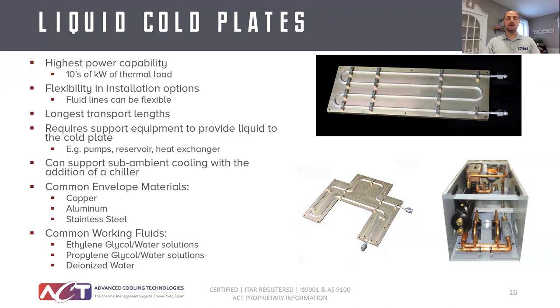Liquid cooling can support sub-ambient cooling if a chiller or chilled water is available, enabling liquid-to-liquid heat exchange to reject high amounts of energy below local room temperature. Envelope materials are most commonly copper, aluminum, and stainless steel. Working fluids tend to be glycol-water mixtures — ethylene glycol or propylene glycol — to suppress the freezing point. Propylene glycol tends to be better for medical applications. Deionized water or saline are also options for surgical devices where you don't want the risk of toxic fluid entering the body.